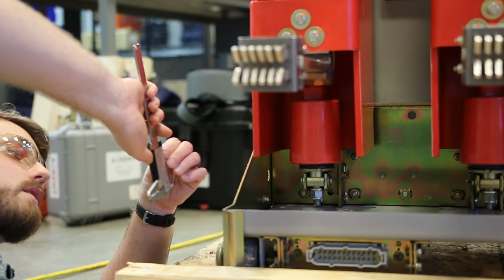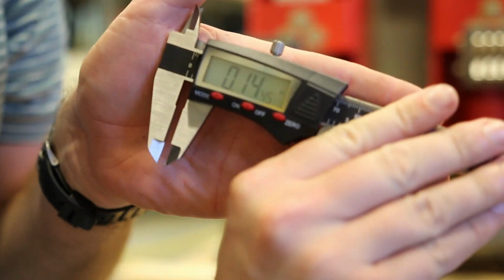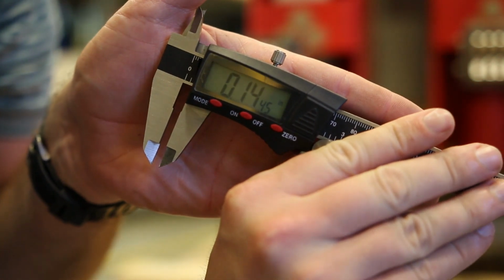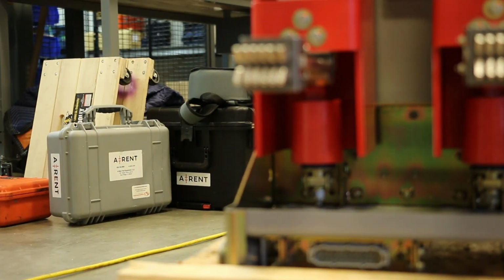All right, so we got that set. Measurement is 0.14 inches. That was miserable to get. We're within tolerance. You would do the same thing on B and C phase. I've already done that, so we are good to go.